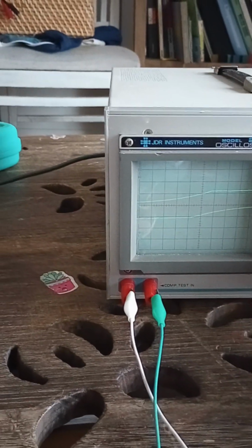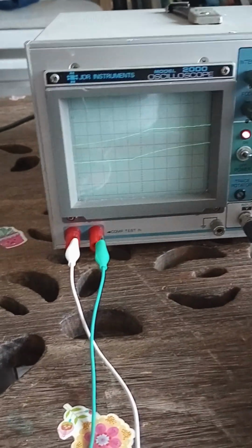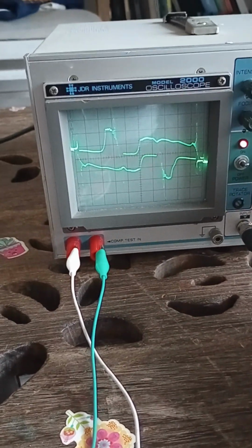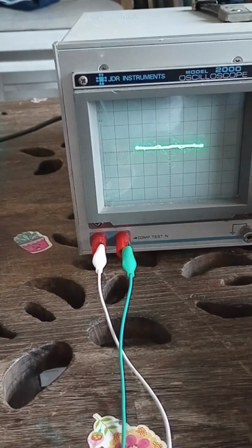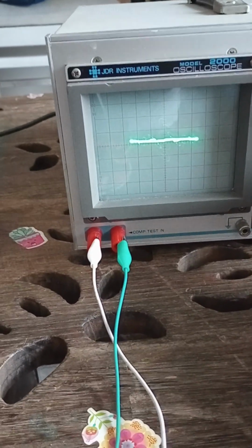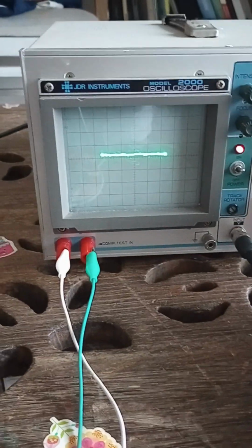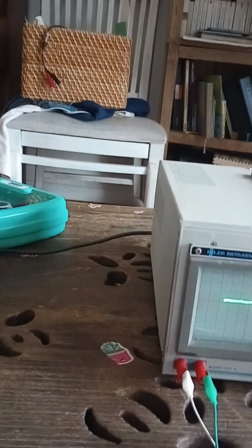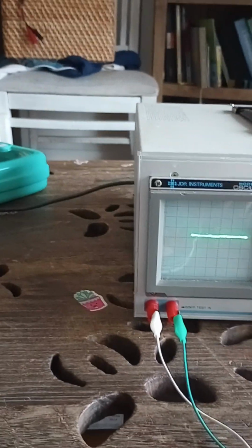So apparently I have a residual current through my lead connected here to the system, and I'm going to adjust the scales. Essentially we should adjust to 2 milliampere per division, and then this will be our 9 volts. All right, so without anything connected, we have voltage that is generated but no input.